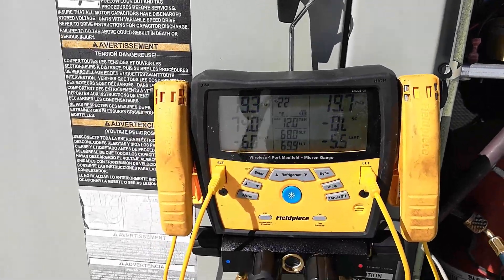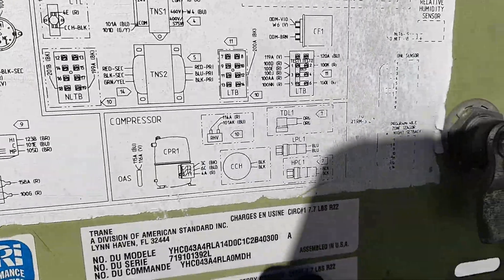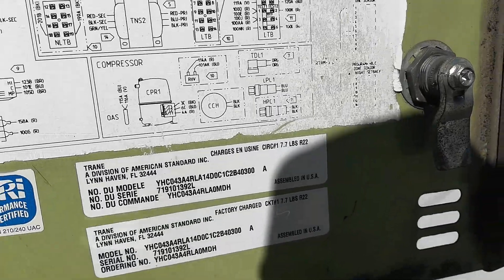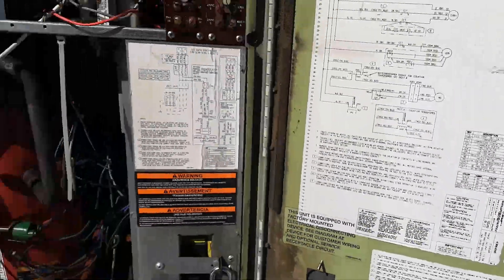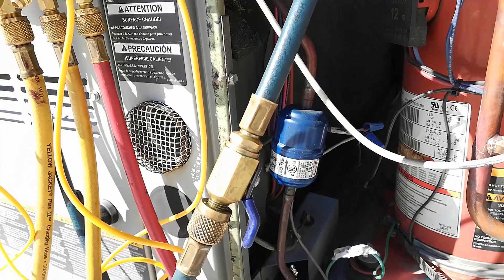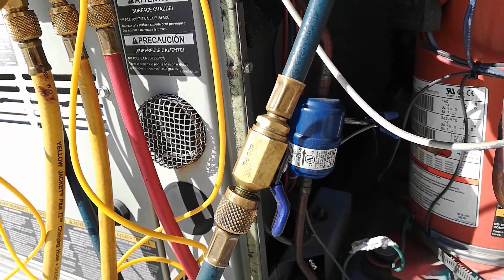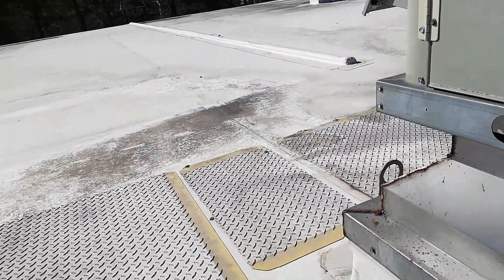It's pulling down pretty fast now. I found the charge on the inside sticker: 7.7 pounds — more than I thought it would be for a 4-ton package. I'll have to replace the dryer today. I think I got an oversized dryer, but it'll be okay as long as it fits. There's 3/8ths as well, and I think that's a quarter, so I'll have to use some fittings on it.